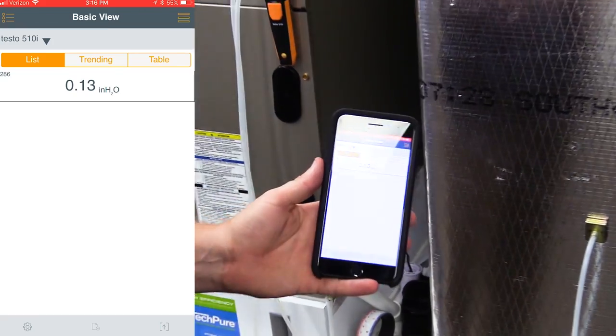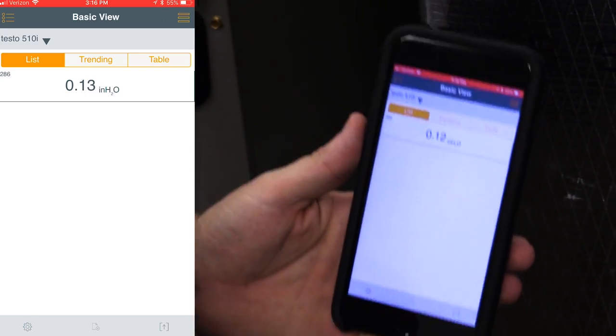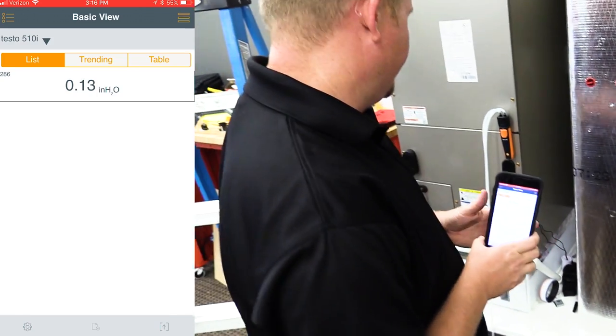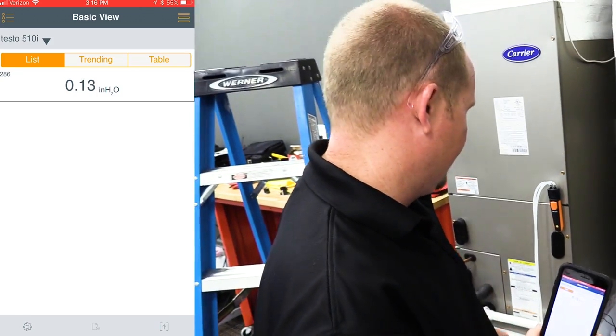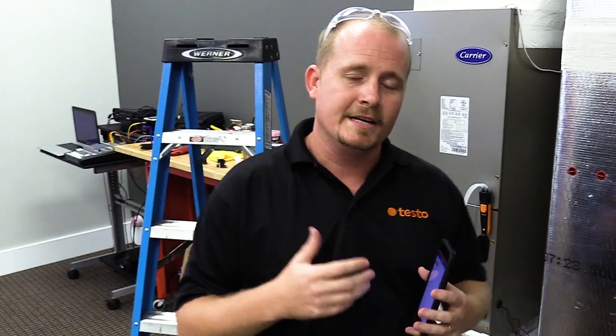So you can see we have a 0.13 inch water column pressure drop across this air filter, which is pretty good given that this is a MERV 11 high-efficiency air filter.